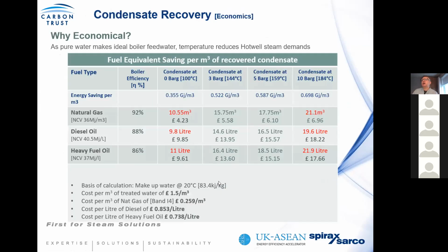If you look at it in financial terms, what we have done here is look at different fuel sources and different condensate temperatures, and you can see there's quite a significant step change between the efficiencies of returning condensate, from a financial and an energy perspective. If you're using something like heavy fuel oil, there's a greater incentive to recover condensate, and you can see in this table what recovering condensate means to your business.